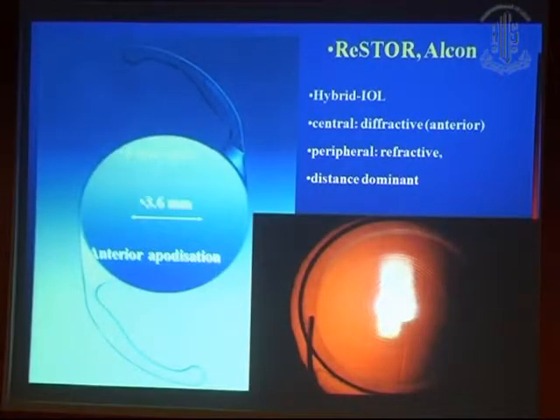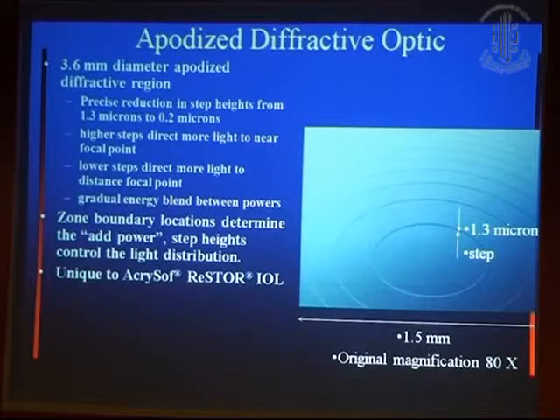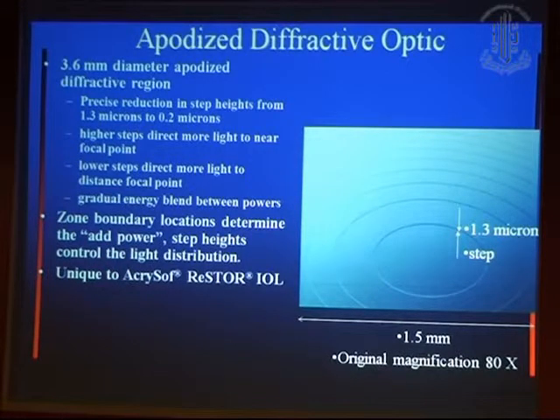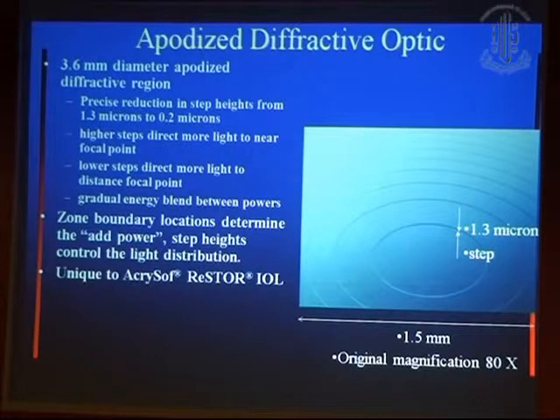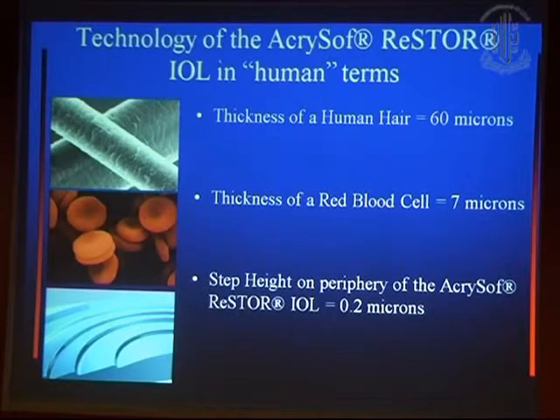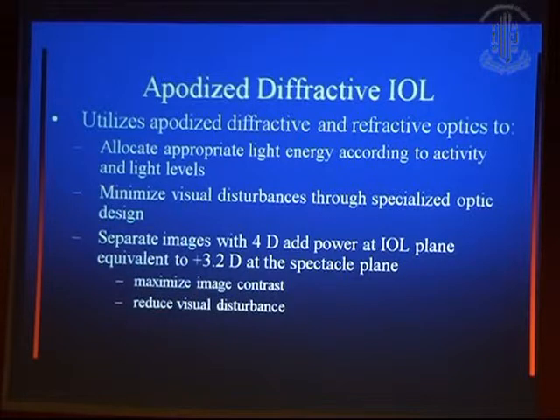The second type has a central 3.6mm of diffractive zones and the peripheral is mono-optic. It is a 3.6mm apodized diffractive zone with precise reduction in step heights from 1.3 micron to 0.2 micron from center to periphery. Lower steps mean more light to distance focus. As the pupil size changes, the amount of light increases or decreases. The thickness of human hair varies around 60 micron, and a red blood cell is 7 micron, but the smallest step is as low as 0.2 micron. The apodized diffractive surface increases light for distance when pupil size is larger and increases light for near when the pupil size is smaller.